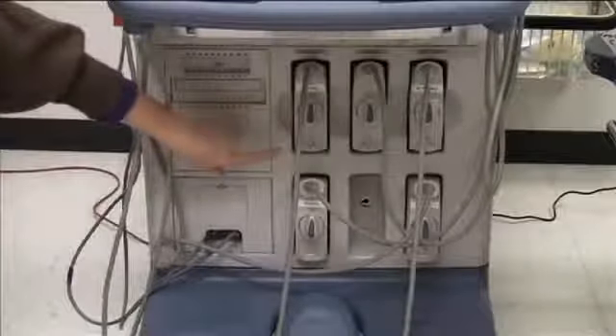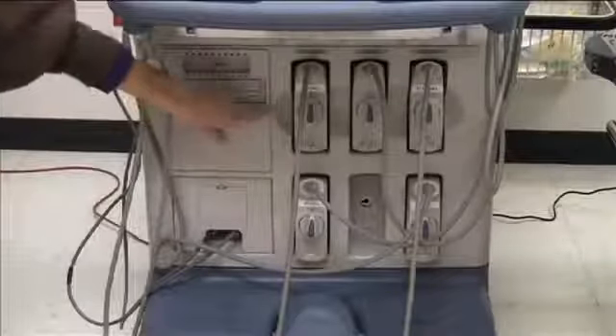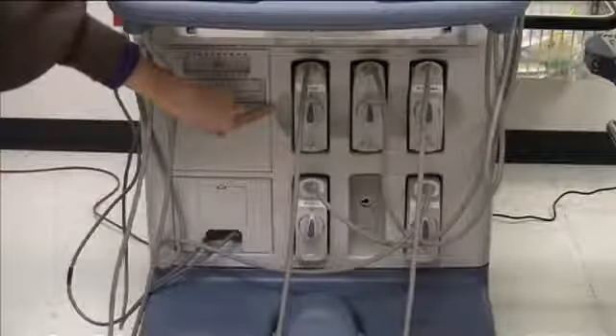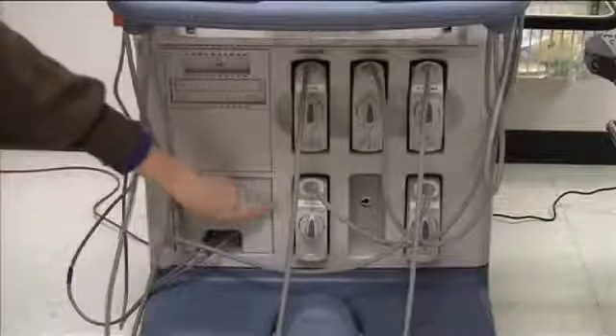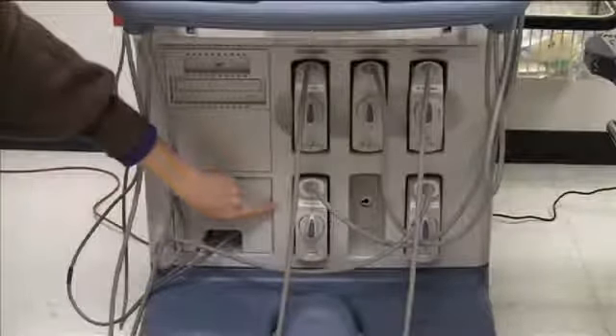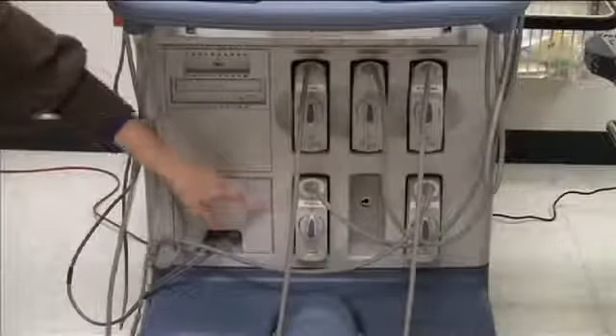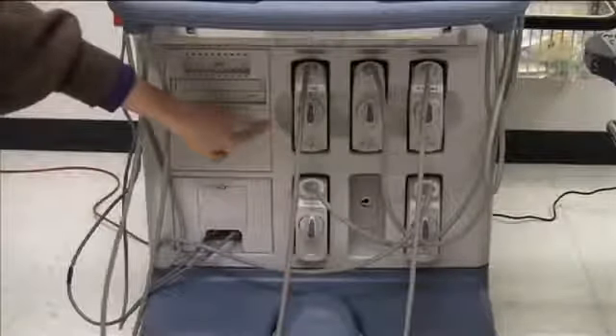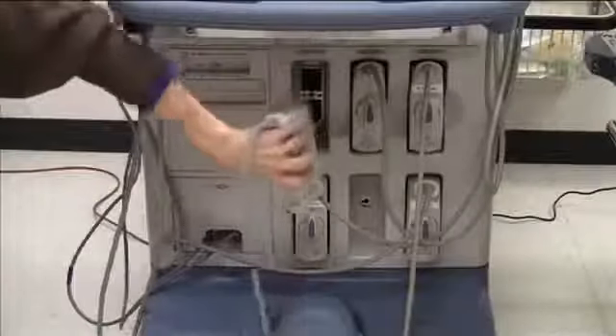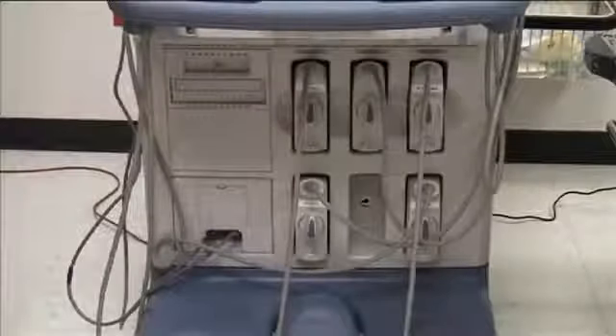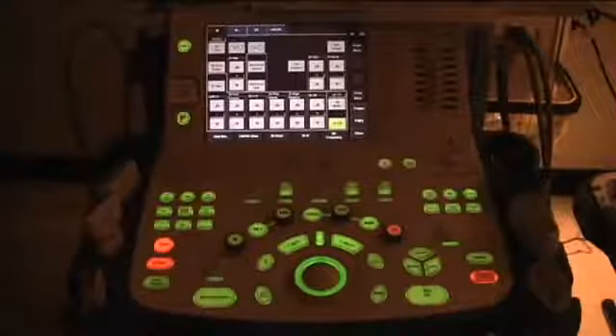Below the machine, you will find the transducer ports. The top 3 slots actually plug into the machine. The bottom 3 slots only are for holding the transducer ports. To change and lock in a transducer's port, flip this knob horizontally and it becomes unlocked. To replace the one you wish to use, insert and turn the knob vertically. Before changing a transducer in the port, you'll want to press the Freeze button.